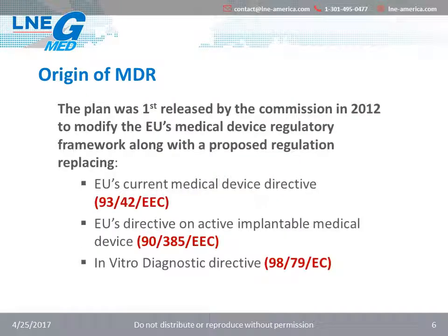The plan was first released by the Commission in 2012 to modify the EU's medical device regulatory framework along with a proposed regulation replacing the following: Current Medical Device Directive 93/42 EEC, Directive on Active Implantable Medical Device 90/385 EEC, and finally the In Vitro Diagnostic Directive 98/79 EC.